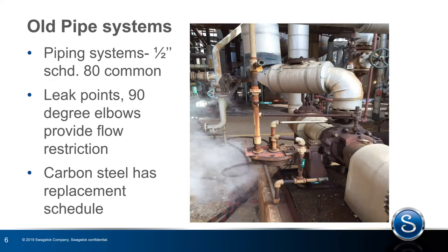This is what I see when I travel around. This particular picture is from one of the refineries on the East Coast, first built as a refinery in the late 1800s. You can see this seal plan has half-inch schedule 80 pipe, a lot of potential leak points, elbows, flow restrictions, and it's made out of carbon steel — you can see it's quite rusty. A lot of plants over the last 20 to 30 years have been working to replace these systems. What I keep hearing from rotating equipment guys is: I've got to get away from threaded piping because of all these potential leak points and reliability or safety issues. By upgrading from carbon steel to stainless steel and moving to tubing, you reduce a lot of those hard 90s and get improved flow.